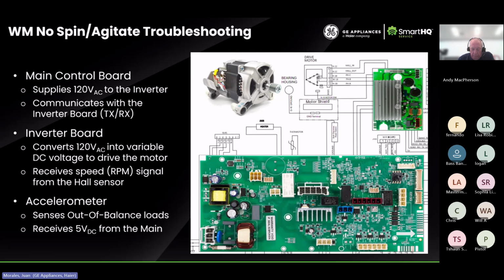It could be higher or lower, but in general they all have to be equal, 3.5 ohms. We also said earlier that the main board supplies 120 volts AC, but I didn't tell you where, and here's where I'm going to show you. Along with the 120 volts AC, there's also DC communication. That blue double arrow means there's communication going back and forth between the main and the inverter.